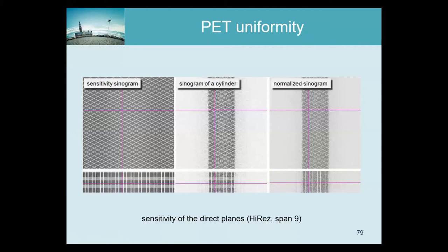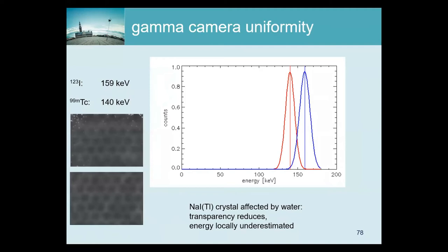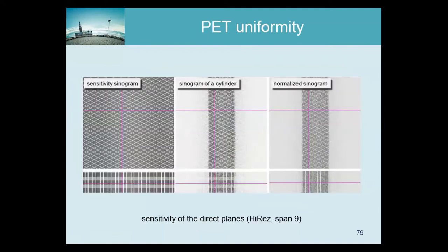This was about uniformity of a gamma camera. As I said, if all goes well it should be nice and uniform. In a PET camera that's very different — here is a PET camera image where all is going well and it's not uniform at all. The reason is that the PET is pixelated and the performance of these pixels is position dependent.